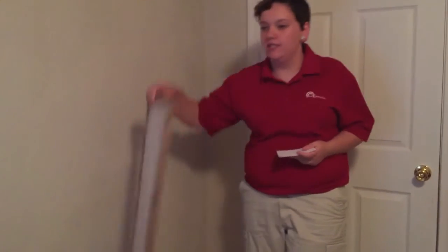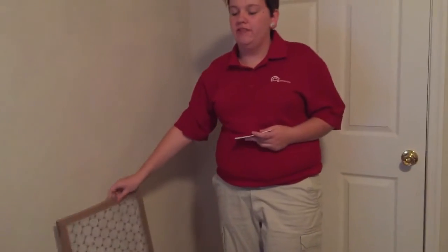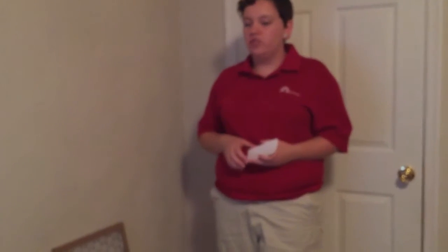Maintenance a technician can do for you. They will clean your outdoor coil as well as the indoor coil, and they will vacuum and remove any debris from the indoor unit as well as the outdoor unit. They will check your air filters, again, referring to this from earlier, to see if they're dirty, and they'll also check the refrigerant pressures to make sure they are normal, and they will check the amps on all electrical components using this meter type of device.